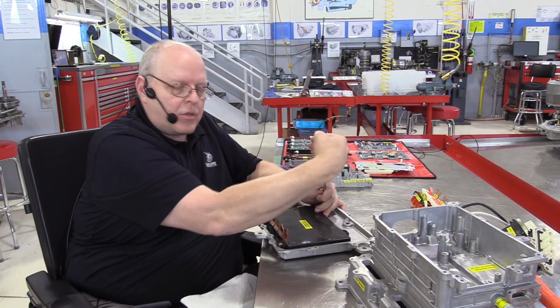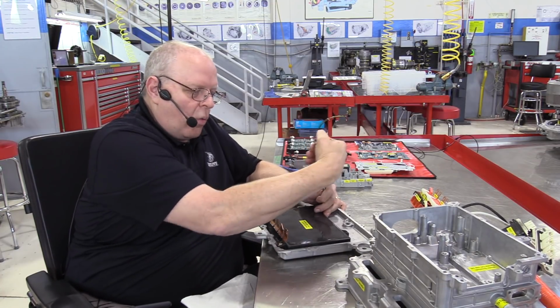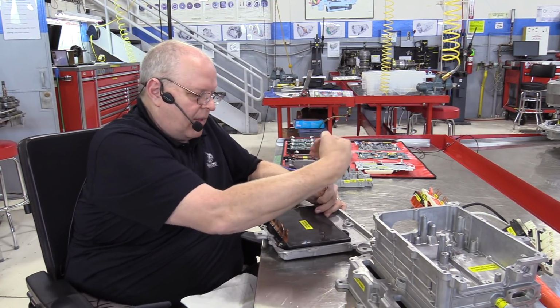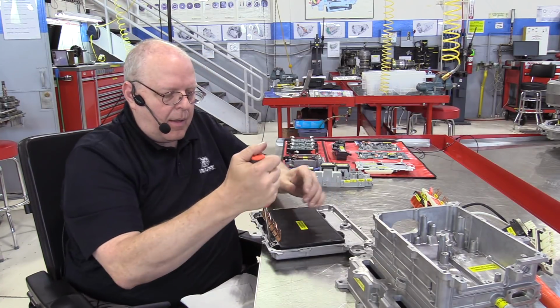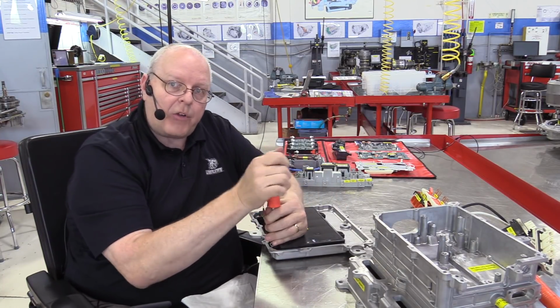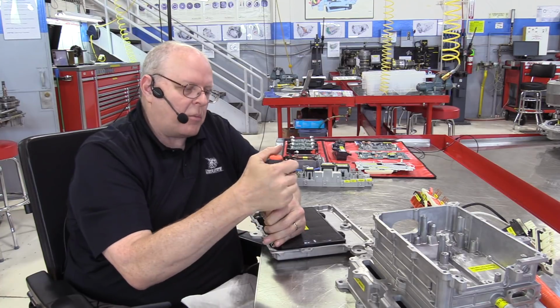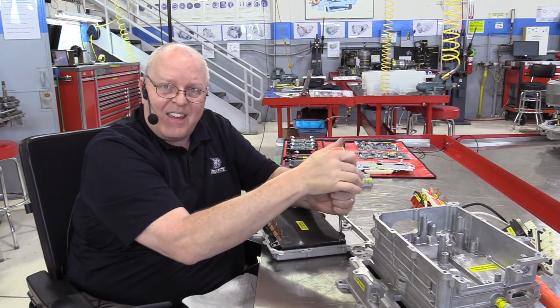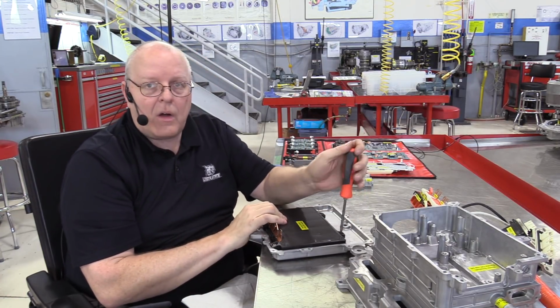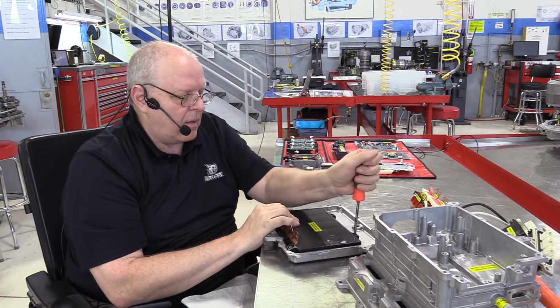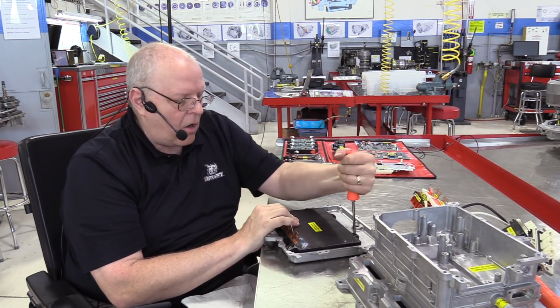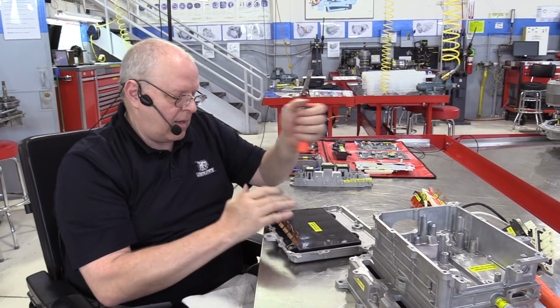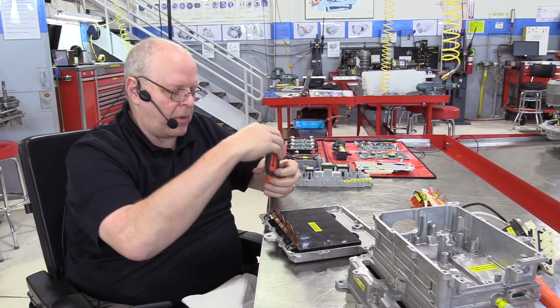But if you charge this capacitor with the negative contactor, as you close the negative contactor, it takes so much current to charge this that it can jump the gap on the contactor's connections and arc and ruin the contacts in a short period of time.